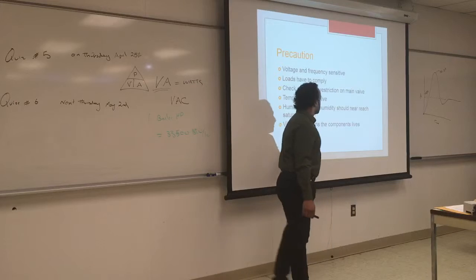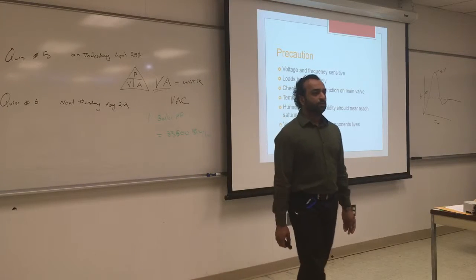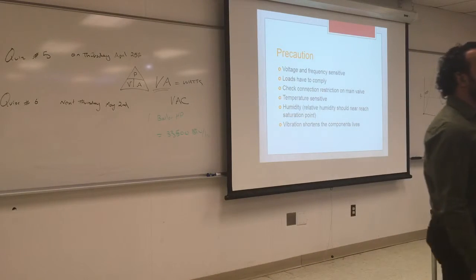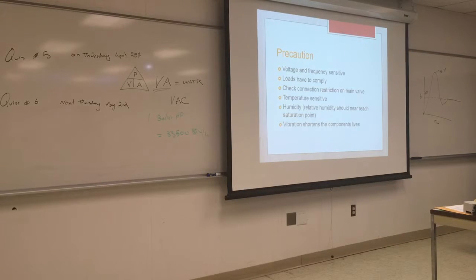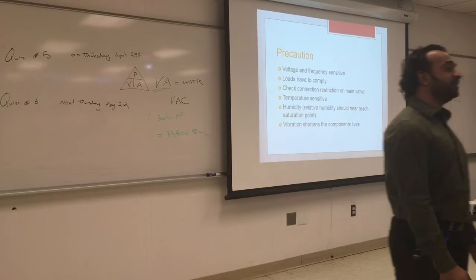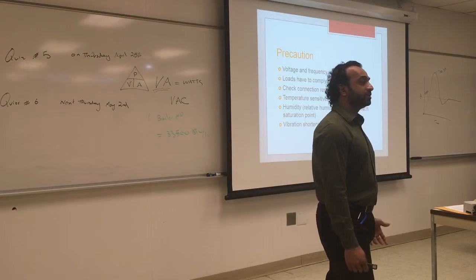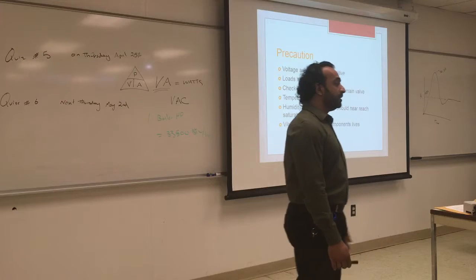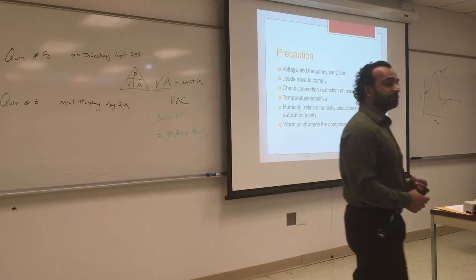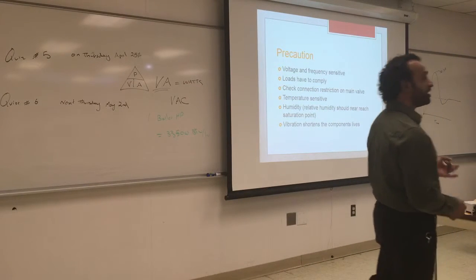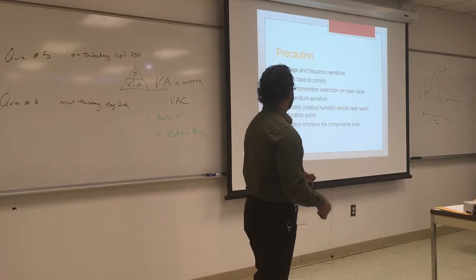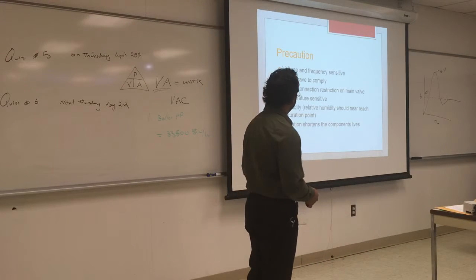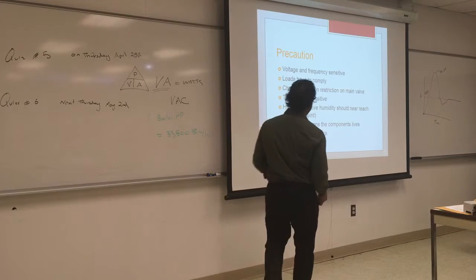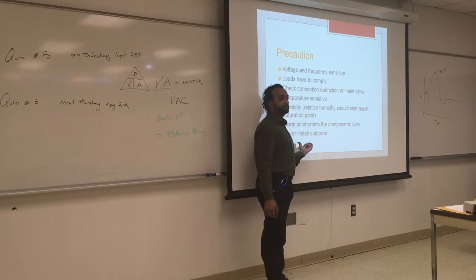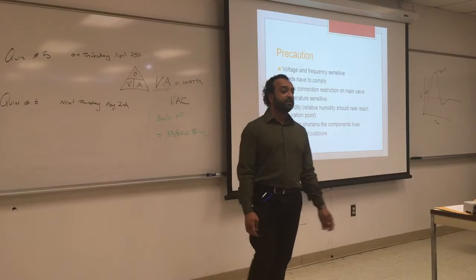Vibration shortens the components' lives. So, what causes vibration in a boiler? Inducer fan, anything that rotates can vibrate over time. So they should not be put close to a place where there's a lot of vibration, or a huge pump, because that will affect your frequency, affect your signals, and affect the soldering of the inside components. So that's something you should think about. They are never to be installed outdoors. They are not designed to be installed outdoors, even inside a box.